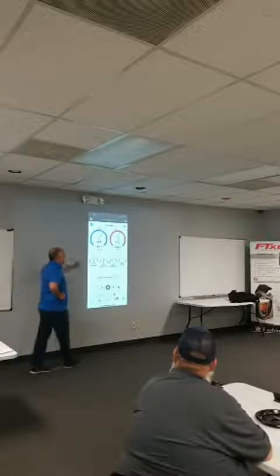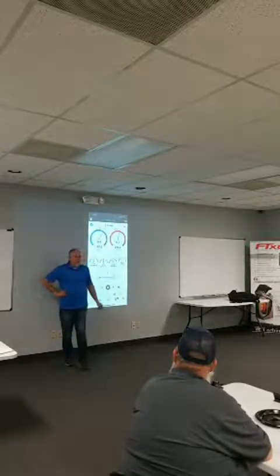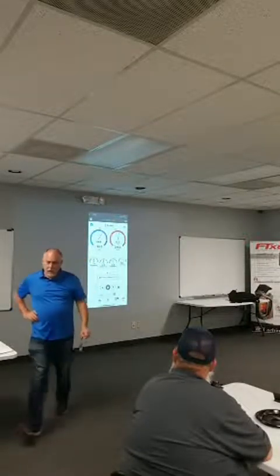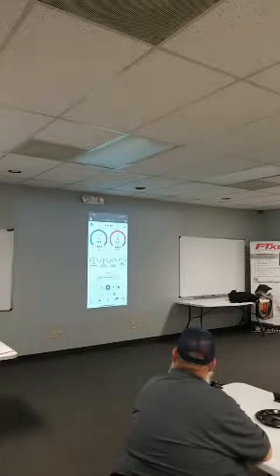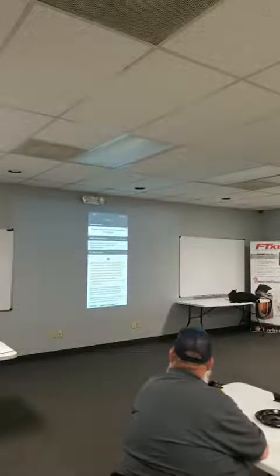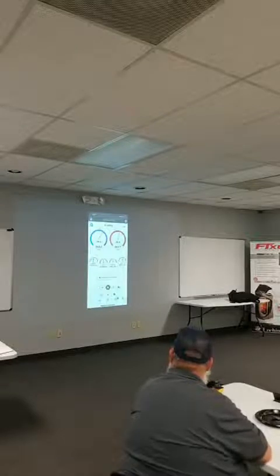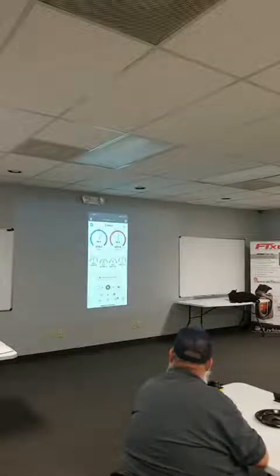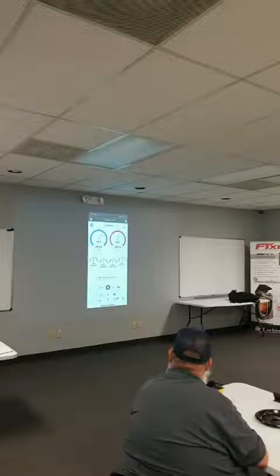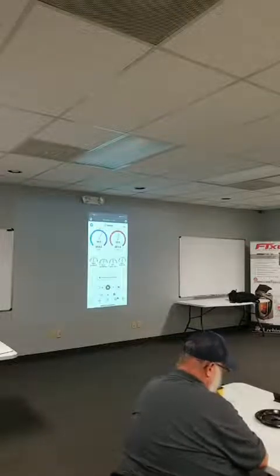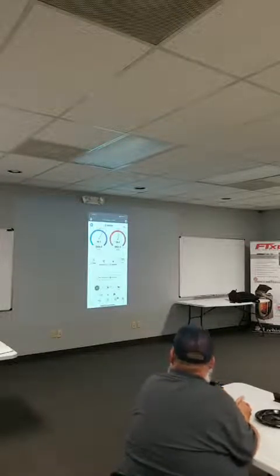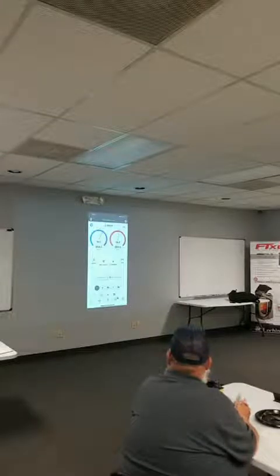Now notice as soon as you flip, this little thing went up there and it's telling you the system's not stable right now. It's going down. Yeah, it's because you just moved the probe over in the supply. So now it should start coming into range a little bit more. Hey, look at that. Now, there's no duct system on this unit, so odds are it's running high airflow. Let's go back to the home screen for just a minute. 368 per ton, that's not really high. Might have an oversized, is that a high efficiency system?